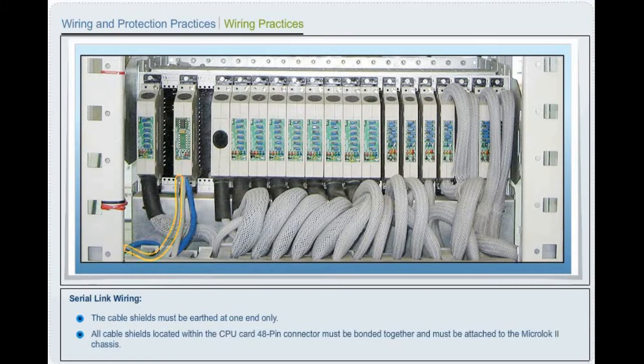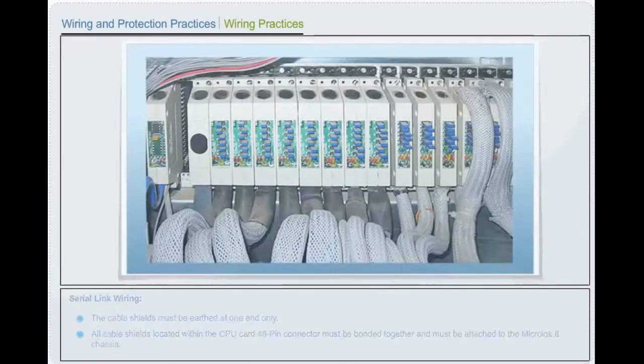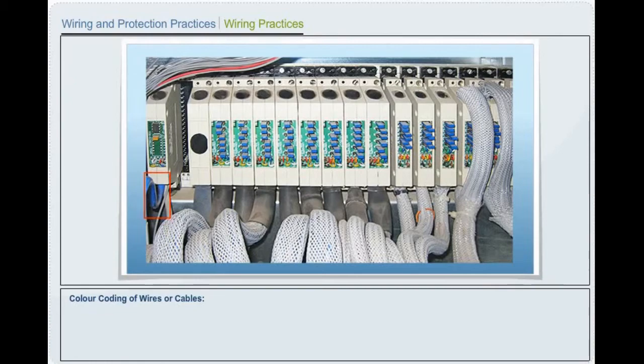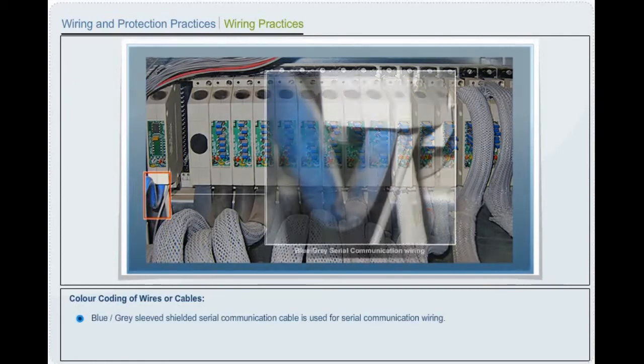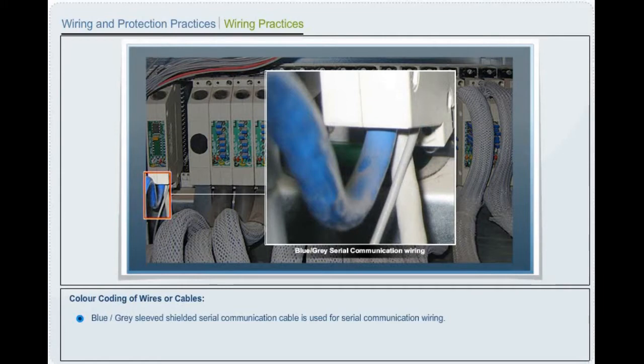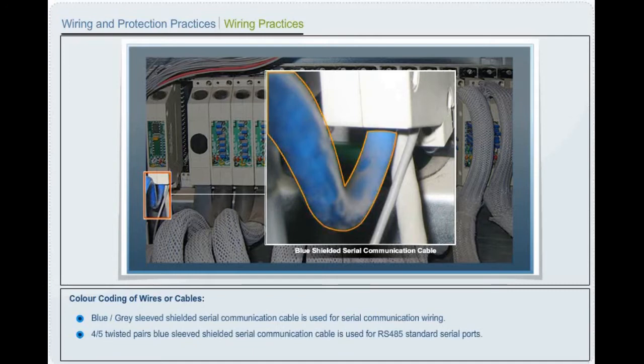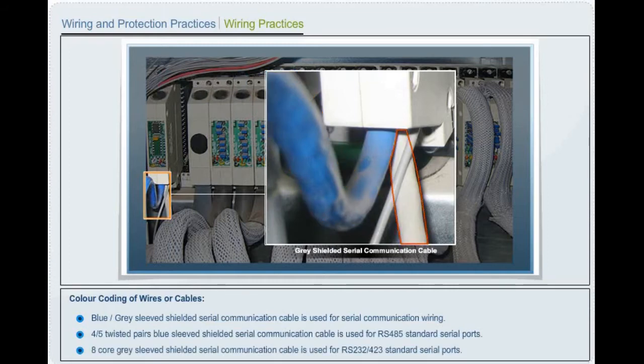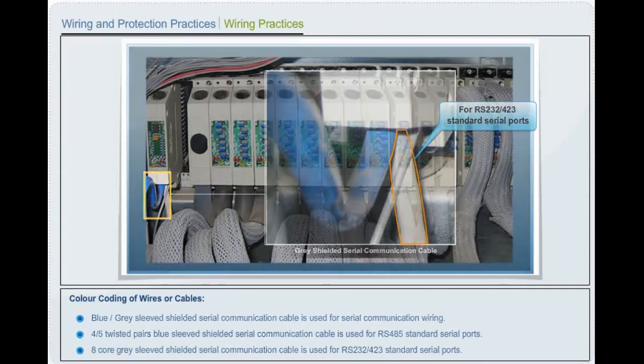All cable shields located within the CPU card 48-pin connector must be bonded together and must be attached to the Microlok II chassis. Color coding of wires or cables. Blue or gray-sleeved shielded serial communication cable is used for serial communication wiring. 4/5 twisted pairs blue-sleeved shielded serial communication cable is used for RS-485 standard serial ports. 8-core gray-sleeved shielded serial communication cable is used for RS-232 or RS-423 standard serial ports.